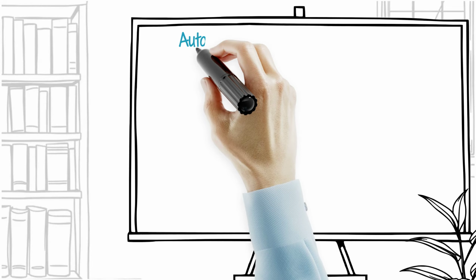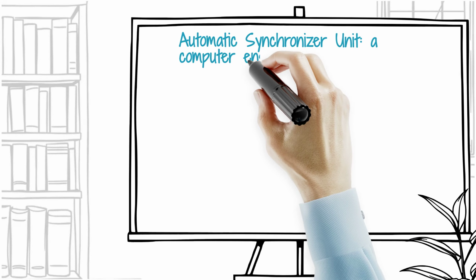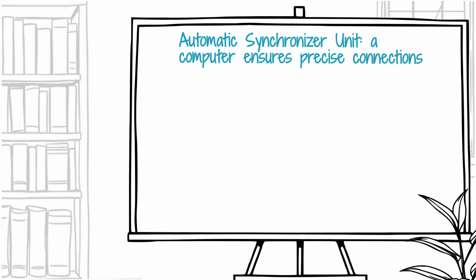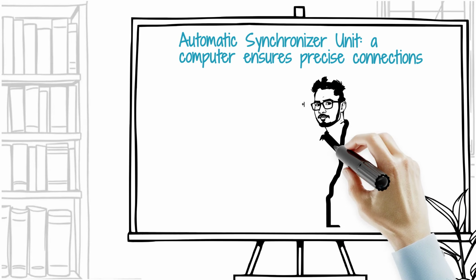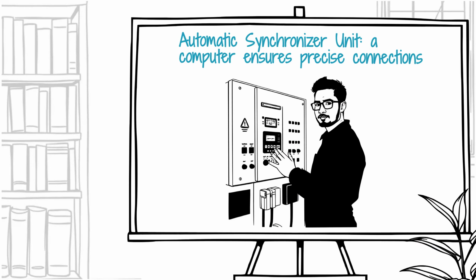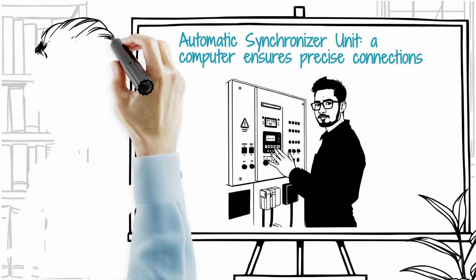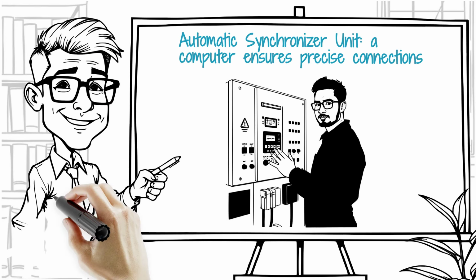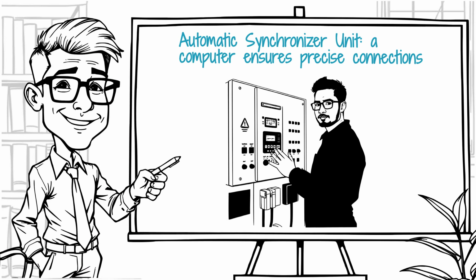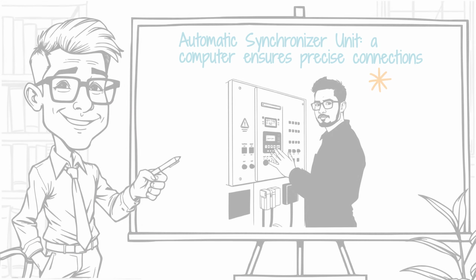Manual synchronization is a high-stakes skill, but modern ships rely on the automatic synchronizer unit to perform this task flawlessly, every single time. This unit is essentially a specialized computer within the main control panel, designed to achieve the three critical conditions for paralleling: voltage matching, frequency matching, and phase angle alignment. Let's break down its intelligence.